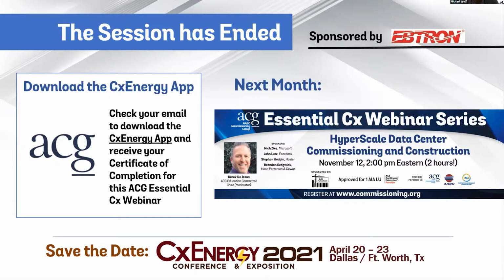We've worked with some clients in Texas about trying to achieve the 2030 goal. And in some cases, that may not be achievable. I talked to a higher ed client with a fairly large campus, and he said that moving their outdoor air damper from 20% to 40% was going to cost an extra $500,000. So this is where, as commissioning professionals, we've got to be thinking creatively. I don't think there's any one magic bullet here, but where I have seen this work well has been, like I mentioned earlier, using occupancy sensors to make sure that we're flushing and purging when we see occupancy. But when we're not seeing that occupancy, we don't need to be running that much air.